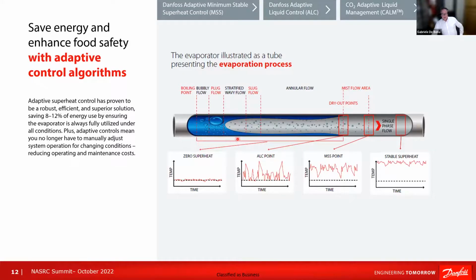In this slide, you can see an evaporator that has been stretched in order to have it as a single straight pipe. The refrigerant that enters the evaporator starts as a mix with a high level of liquid and some part of vapor. It starts to evaporate throughout the pipe of the evaporator.